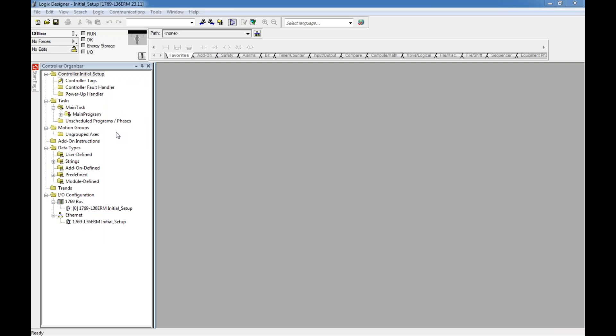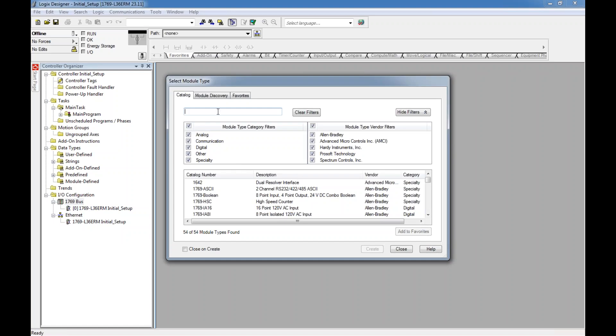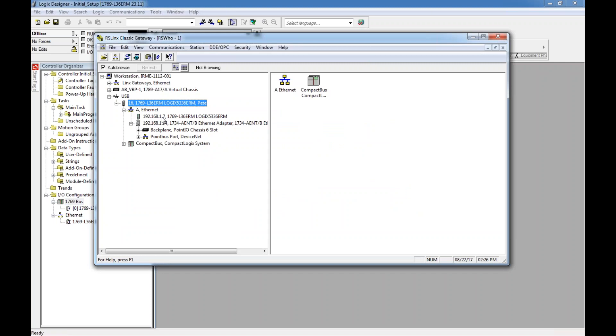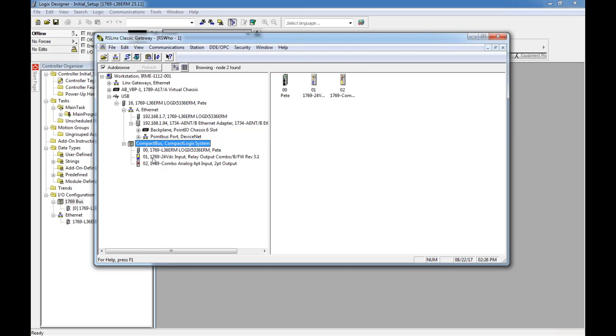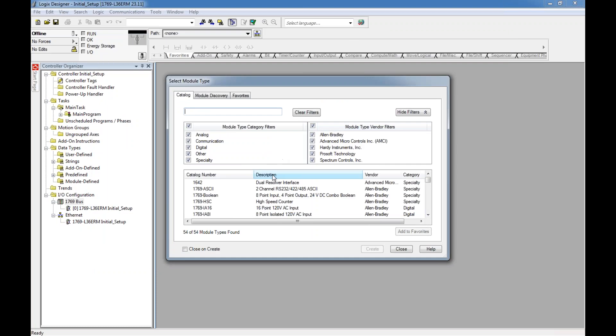The project is now loaded — notice I have nothing under my IO Configuration. For any programming I need hardware listed there. First, I right-click on the 1769 bus — that's the backplane — and click New Module. I can look up a compact bus to see it's a 1769 IQ6 24-volt input card. I can read the module number directly off the input card itself: 1769-IQ6.